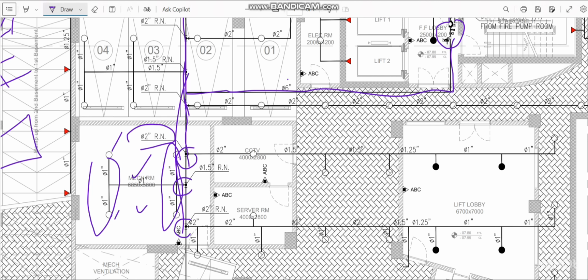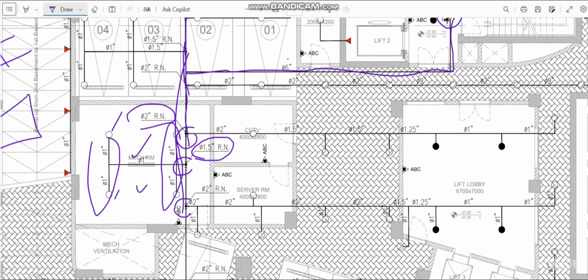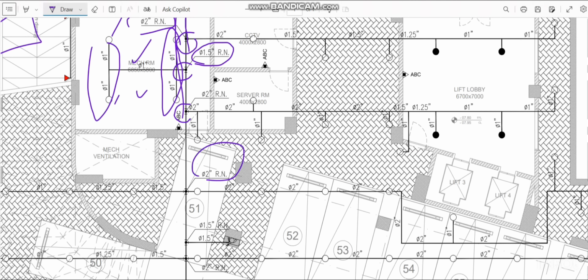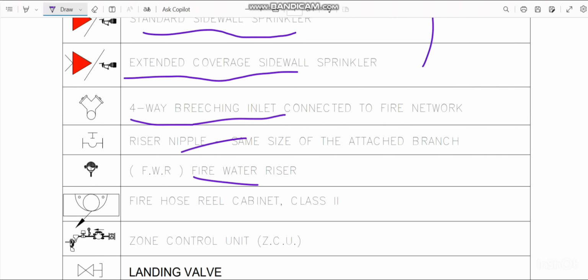So 4 sprinkler means I have used the 1.5 inch riser nipple. Whenever you are taking the branch, like here also you can see a 2 inch riser nipple, you have to provide the riser nipple. The next two items are only the fire hose reel cabinet and zone control valve. Zone control valve, I just now explained, it was near to the riser, and we will see the fire hose cabinet at this point.